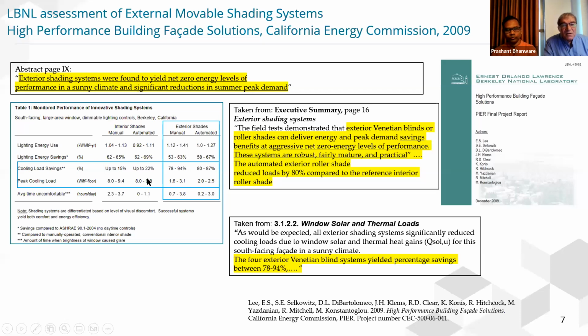And on this table, you can see for interior shade, the potential reduction of cooling loads compared to a single clear glass or a double clear glass is in the range of 15 to 20%. The moment you have an external shade, whether it is manual or automated, the ratio changes a little bit. The cooling load through the window is reduced by about 85% in both cases. And the peak cooling load in relation to the solar heat gain is reduced by a factor of more than 4. You can see that the maximum cooling load is in the range of 8 to 9 watts per square foot, which means almost 100 watt per square meter of heat gained through the window, compared to 1.6 to 3 watts per square foot, around 20 watt per square meter, in the case of external shading.